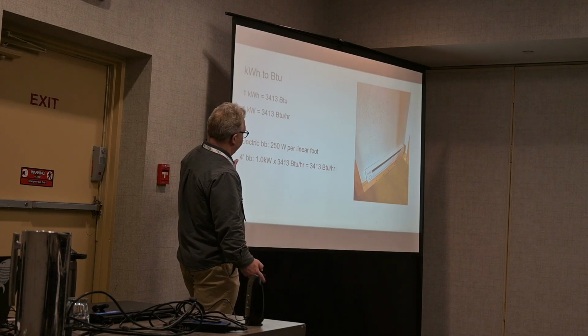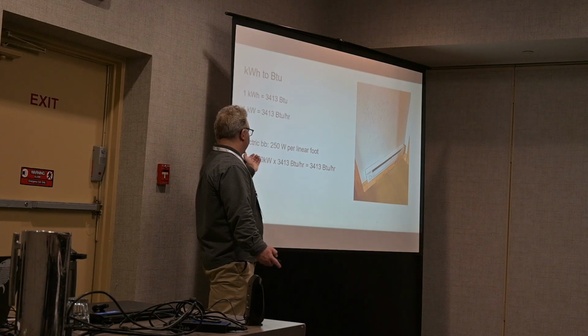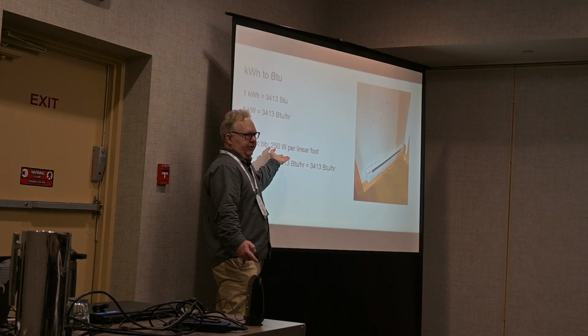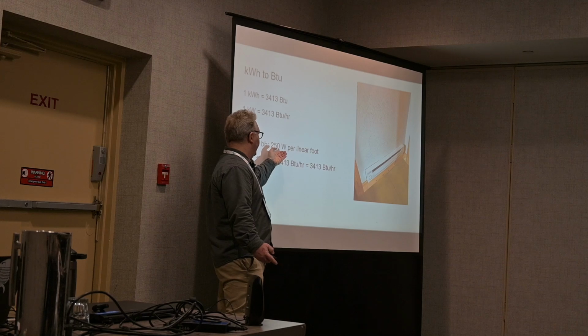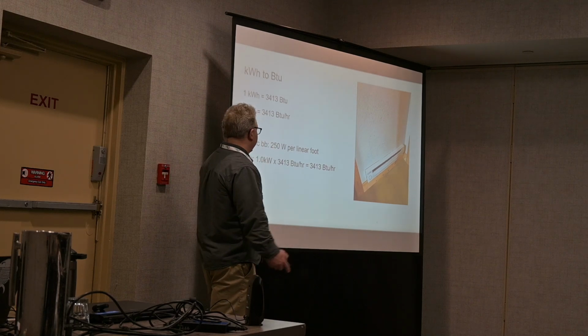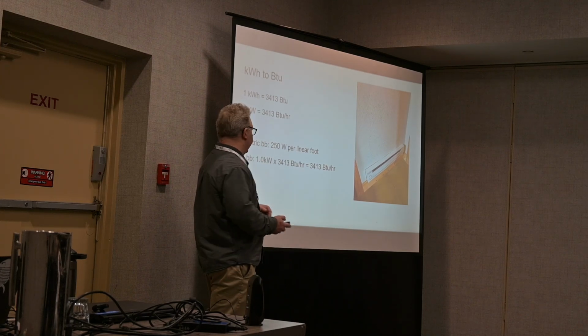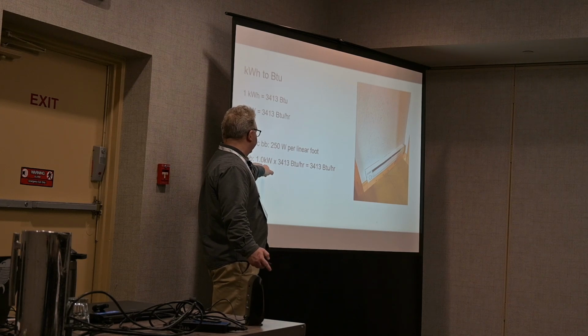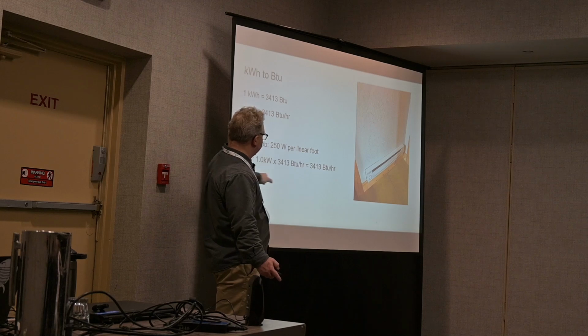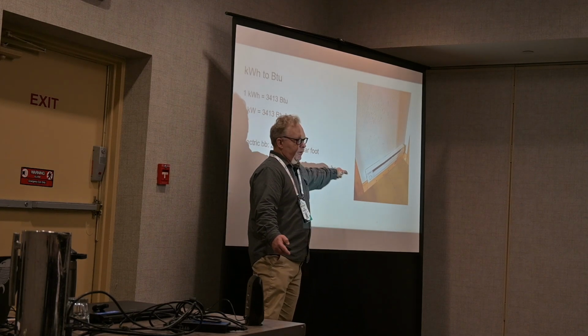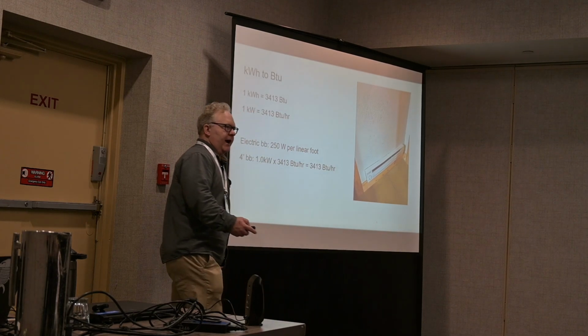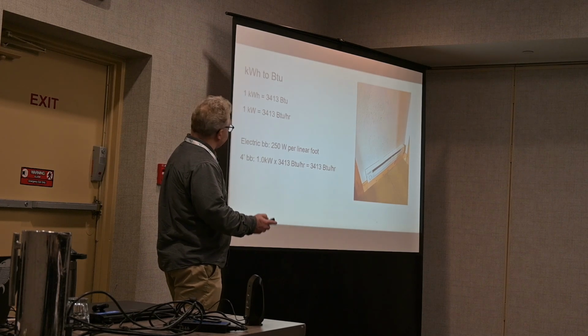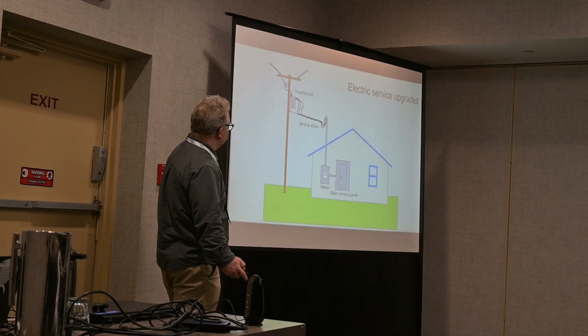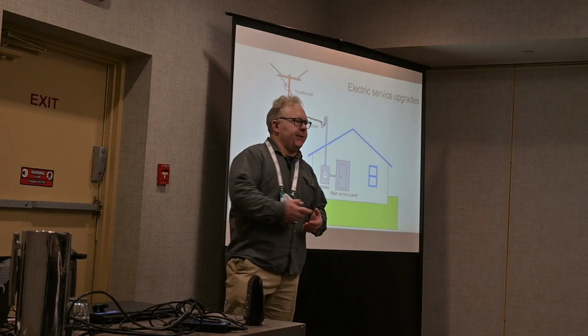And so if we have a standard electric baseboard, it's typically 250 watts per linear foot. We have a 4-foot long baseboard. That's going to be 1,000 watts or 1 kilowatt. And we can calculate that that'll deliver 3,413 BTUs per hour. Okay, so that's it for the basics.